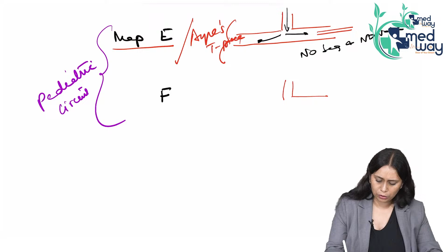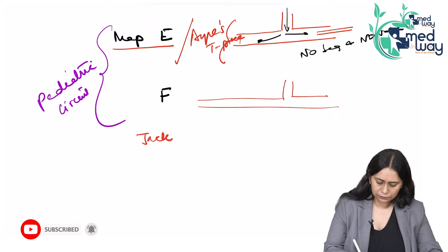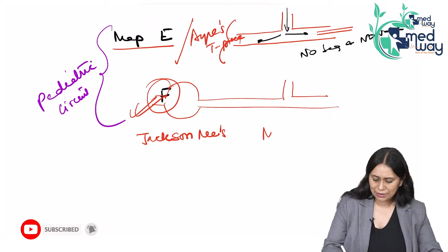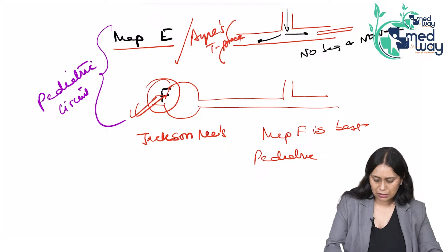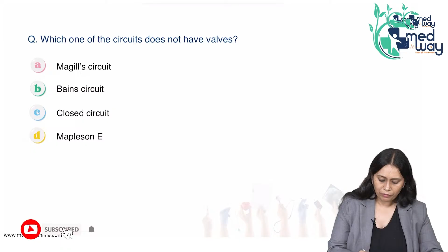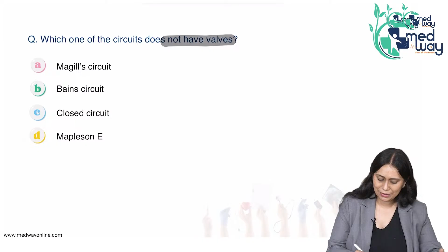It has no bag and no expiratory valve, bagless and valveless. Now this circuit was not very useful, so the same circuit was taken by a person called Jackson Rees, and what Jackson Rees did was attach a bag to it. Now this became Mapleson F. Mapleson F is the best circuit in pediatrics for any type of ventilation. This is the only pediatric Mapleson circuit which we are using. So Mapleson F is the best pediatric circuit, or we call it the Jackson-Rees circuit. So the question is, which one of the circuits does not have a valve? The answer is Mapleson E, or we call it Ayre's T-piece.